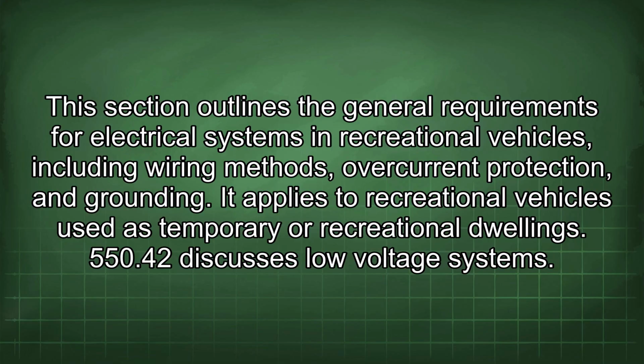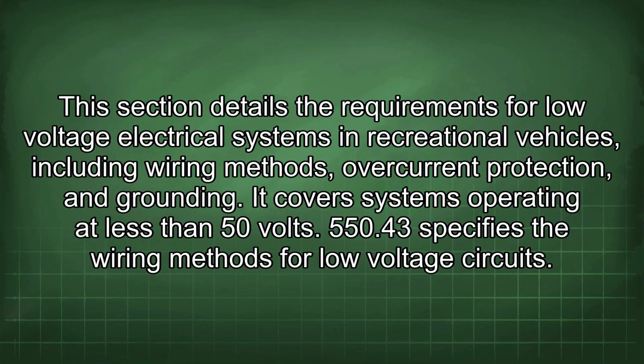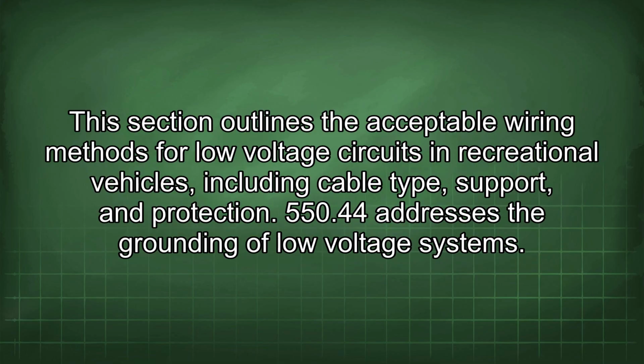550.42 discusses low-voltage systems. This section details the requirements for low-voltage electrical systems in recreational vehicles, including wiring methods, overcurrent protection, and grounding. It covers systems operating at less than 50 volts. 550.43 specifies the wiring methods for low-voltage circuits. This section outlines the acceptable wiring methods for low-voltage circuits in recreational vehicles, including cable type, support, and protection.